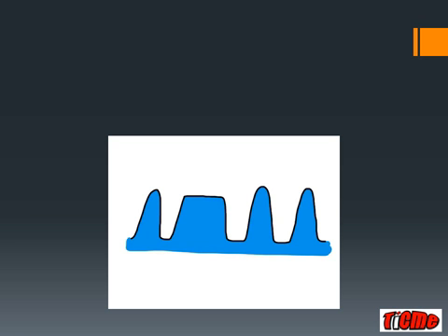What about this one? What we've got in the second breath is a nice square waveform plateaued breath, usually consistent with a ventilator breath. Either side of that, there's sort of smaller, shorter, less deep breaths. Any idea what this is? Yep, so this is a breathing patient who's got SIMV ventilation and they're breathing spontaneously, and there's a ventilated breath as well.